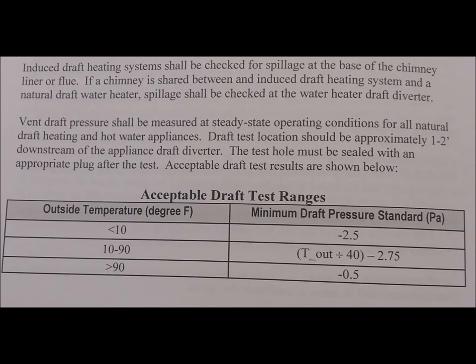Acceptable draft test results: Outside temperature less than 10°F: negative 2.5. Between 10°F and 90°F: delta T out divided by 40, minus 2.75. More than 90°F: negative 0.5.